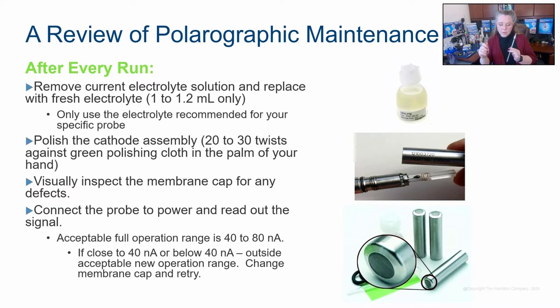It's going to be better or it's not. Honestly, if you've replaced the cathode assembly, the cap, and the electrolyte, you've basically got a brand new probe for all intents and purposes. So if it doesn't work after that, there's something wrong in the electrical of the probe and you just need to replace the probe. Okay. This does take a little bit of time. These are what we call high maintenance probes. If you do not do this after every run, you will have consecutively and sequentially worse performance.